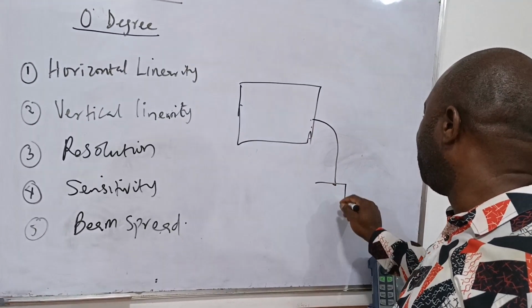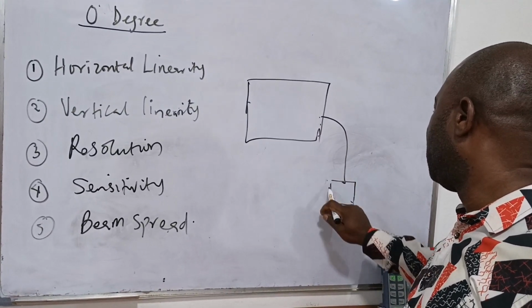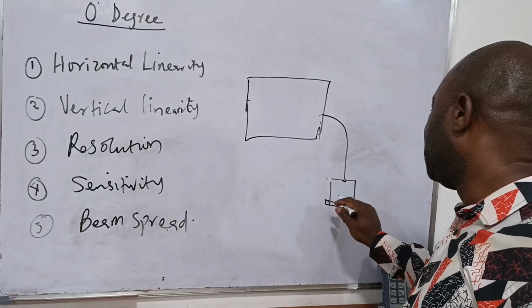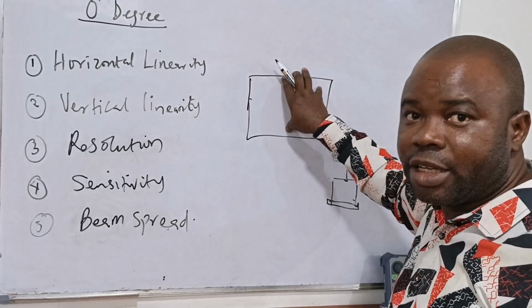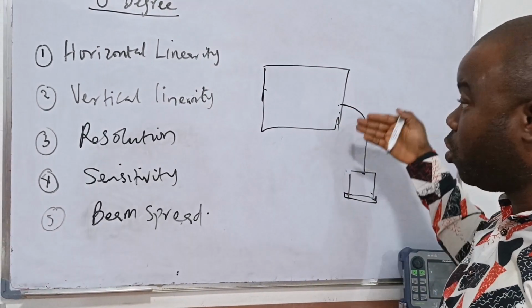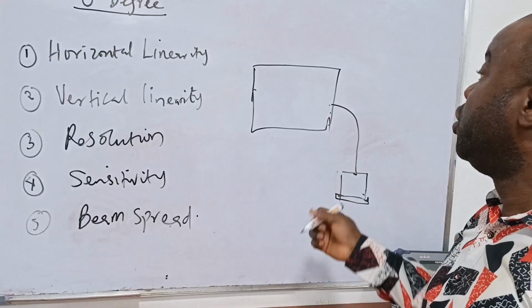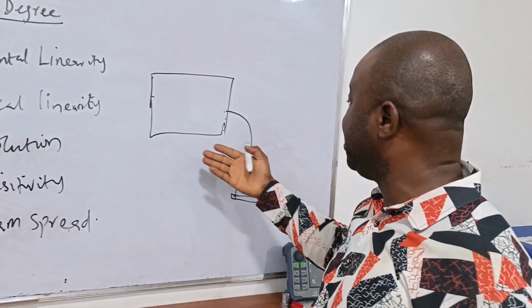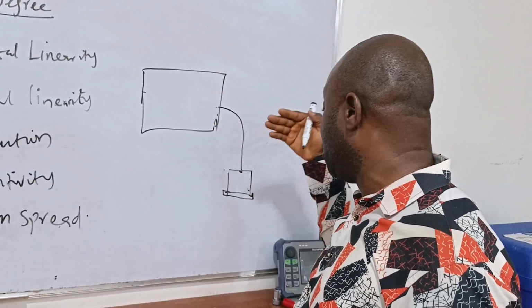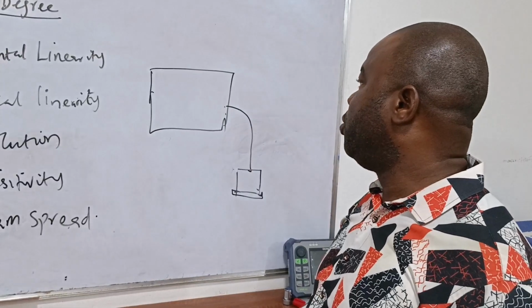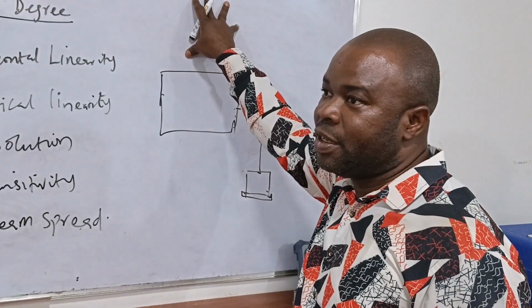connected to a probe, so this is the flaw detector, this is the probe, this is your coaxial cable, and it's connected. You want to check if this machine, while connected to the probe, is working properly.